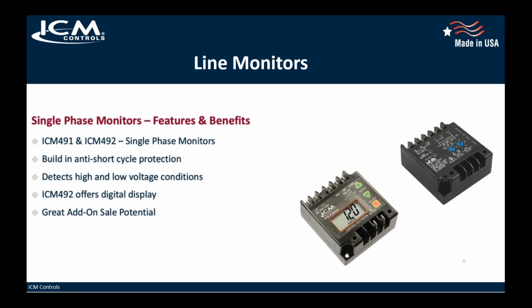These both do very similar things, only that the 492 is a little bit more advanced, being that it has a control voltage, and it also has a digital display with a 5-fault memory and built-in anti-short cycle protection. So this voltage monitor will detect brownout conditions and high voltage conditions, and you're tied in parallel with the main line coming in. So we're constantly monitoring that line, and then we'll open up a dry contact relay that's rated for 10 amps. Basically, what that's intended to do is break a control circuit that shuts your system down in case we see a brownout condition.